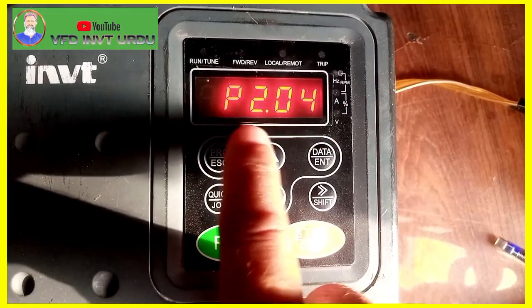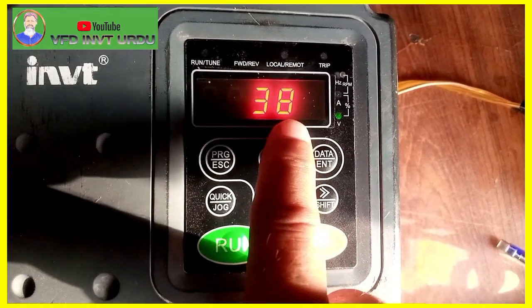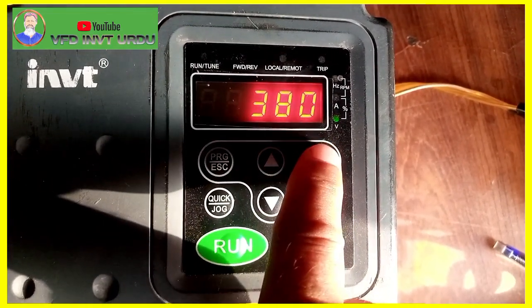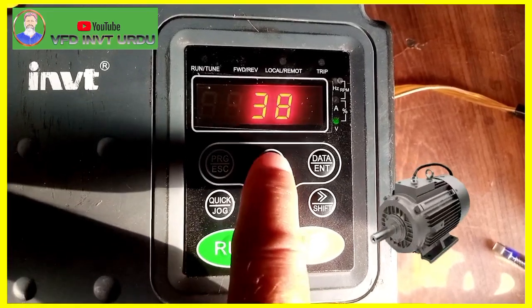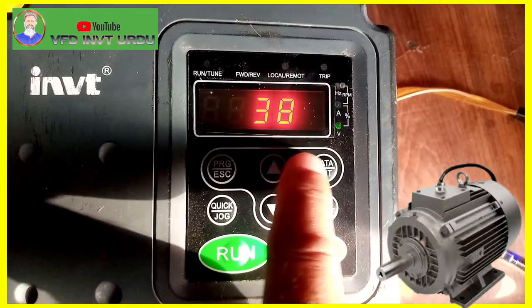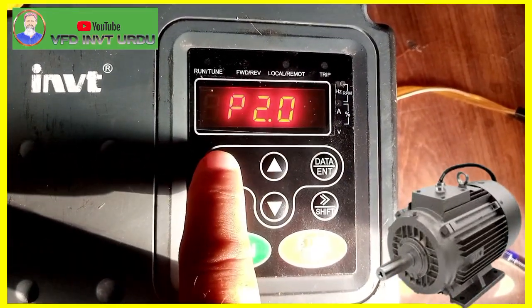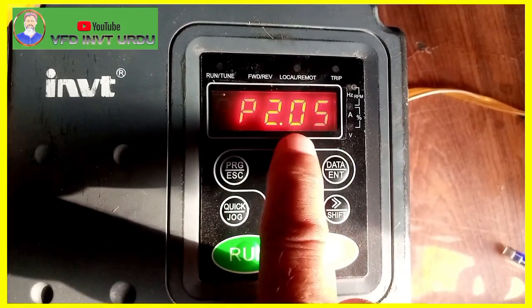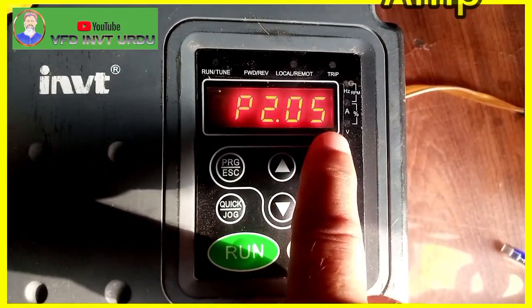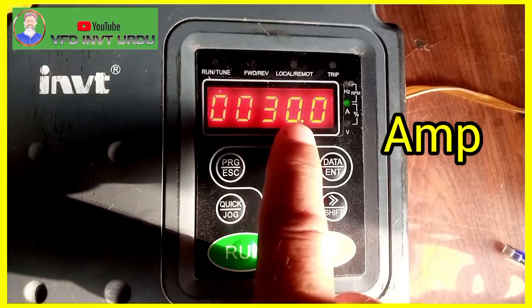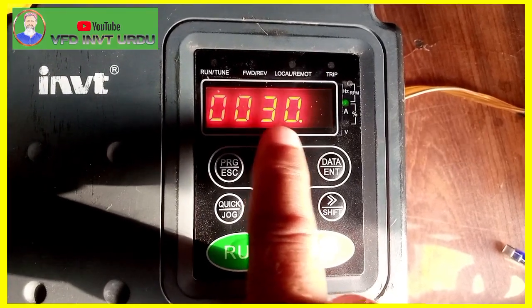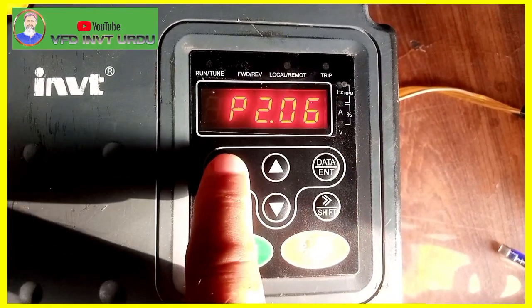P2.04. This is the motor voltage. Most motors run on 380 volts. Some motors use up to 415 volts. Enter the correct voltage and press data. P2.05. This is the motor current in amps. Check your motor nameplate and enter the right value. Press data to save. P2 setting complete.